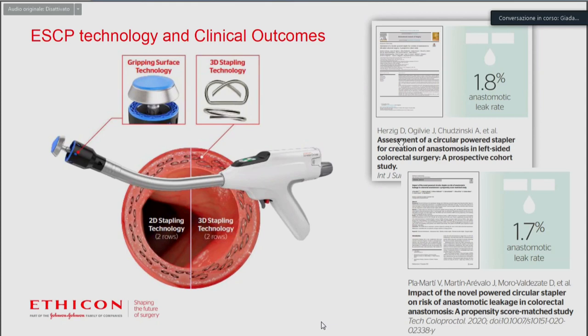That incorporates many of the technological innovations that we've been seeing on the previous slides. As you see, we've been incorporating here the gripping surface, which gives the possibility to apply compression just where it's mostly needed, so where the staple will form.